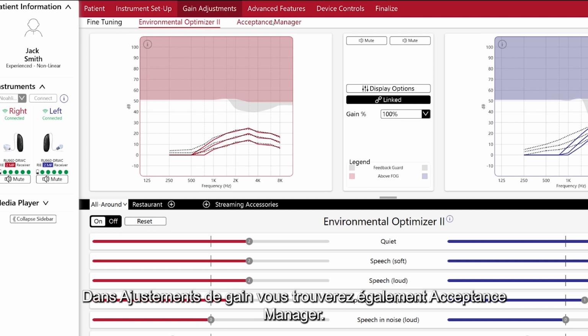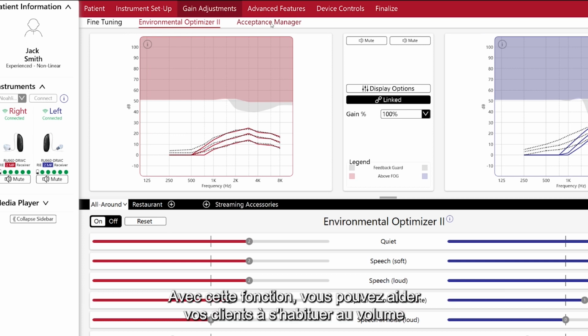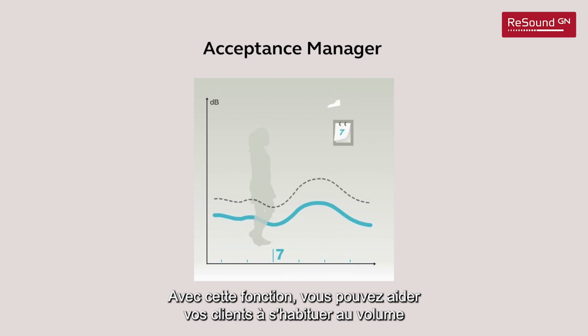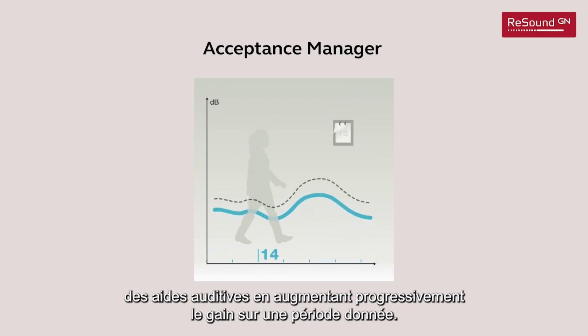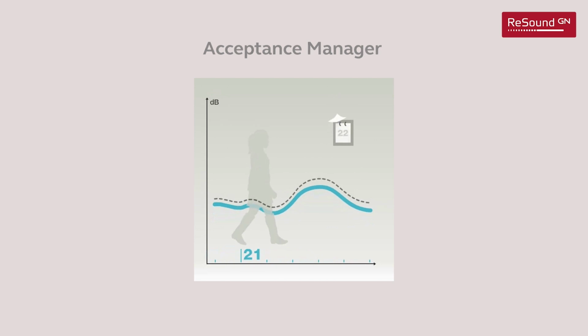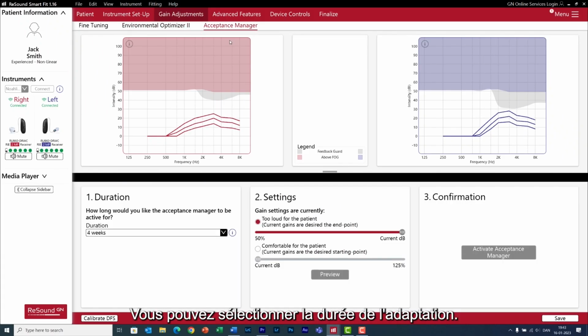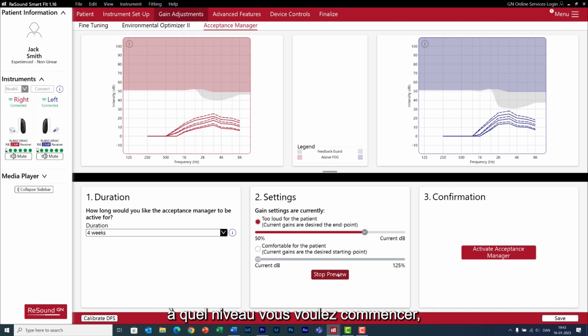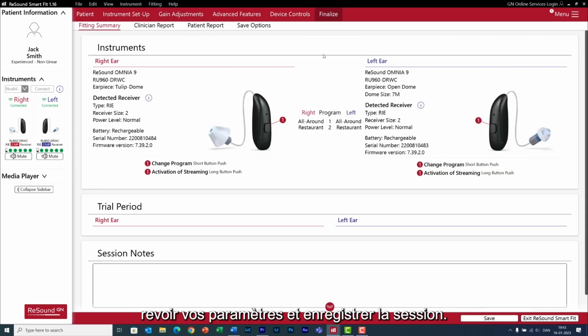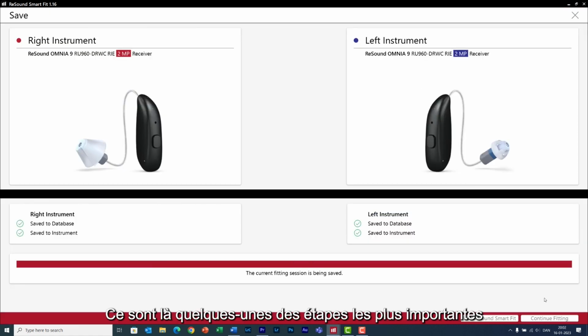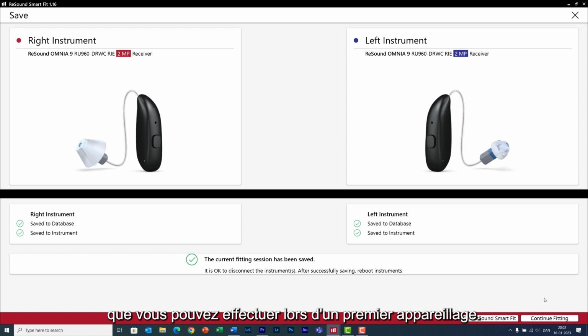In Gain Adjustments, now you will also find the Acceptance Manager. With this feature, you can help your clients get used to the sound of the hearing aids by gradually increasing the gain over a period of time. It's very easy to use. You can select for how long you want the adaptation to be. Then you can lower the gain to decide at what level you want to start from, and activate the Acceptance Manager. And when you are happy, you can go to Finalize, review your settings, and save the session. These are some of the most important steps that you may want to consider during a first fit.